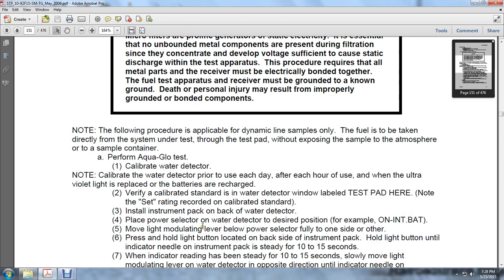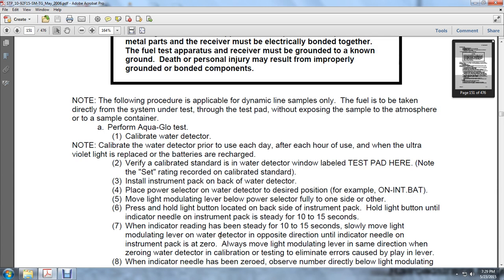Move the light modulating lever below the power selector fully to one side. Press the hold and light button located on the back side of the instrument pack. Hold the light button until the indicator needle on the instrument pack is steady for 10-15 seconds. When the indicator reading has been steady for 10-15 seconds, slowly move the light modulating lever on the water detector in the opposite direction until the indicator needle of the instrument pack is at zero.